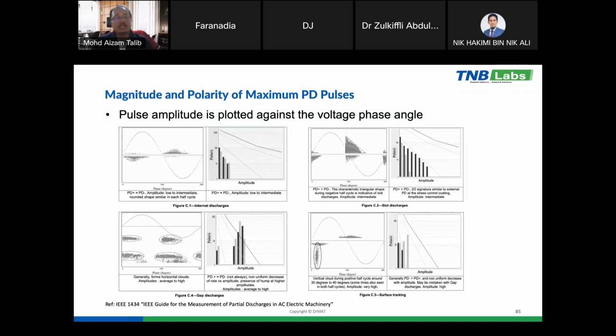Okay, what is the advanced analysis for the PD detection? Here, IEEE has come up with the measurement of PD in AC electric machinery. They suggest the analysis of the magnitude and polarity of the maximum PD pulse. So we plot the pulse amplitudes against the voltage phase angle. Here is the phase resolved PD pattern, the plot of the PD pulse against the phase angle. From this pattern, we are able to differentiate between the noise and the actual PD.